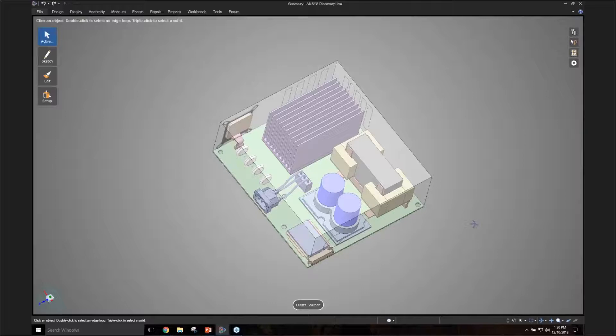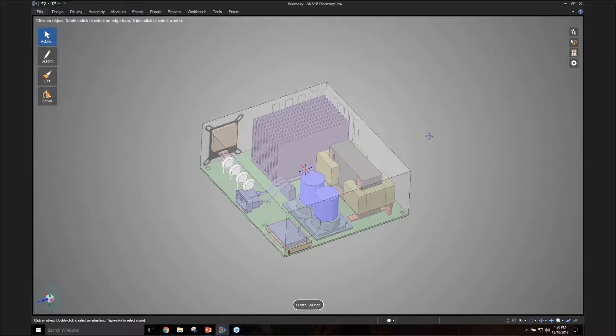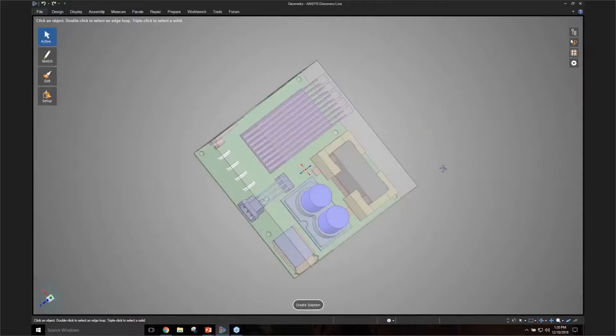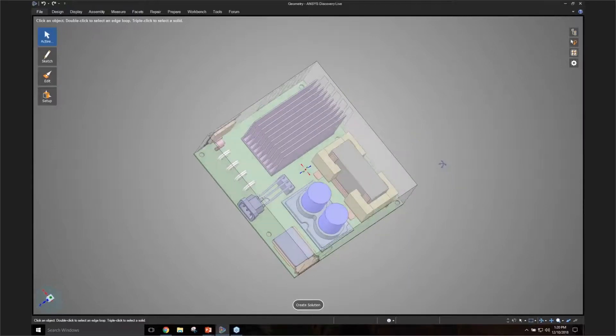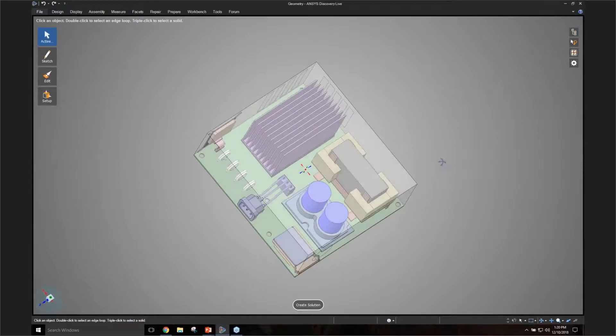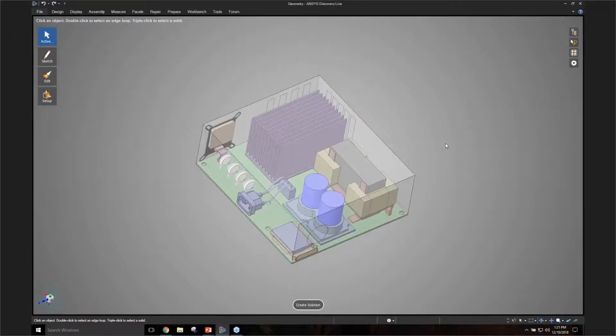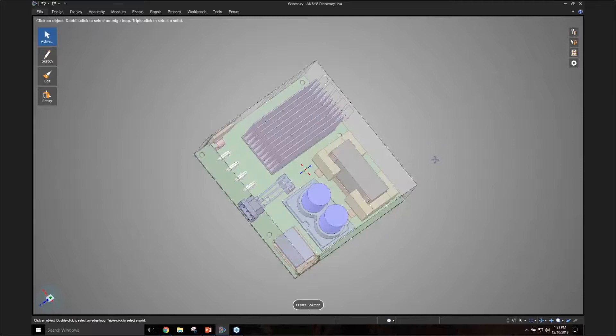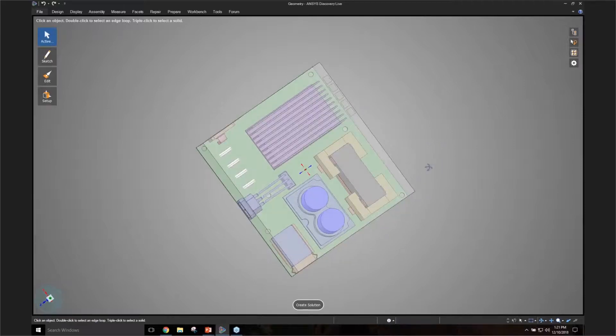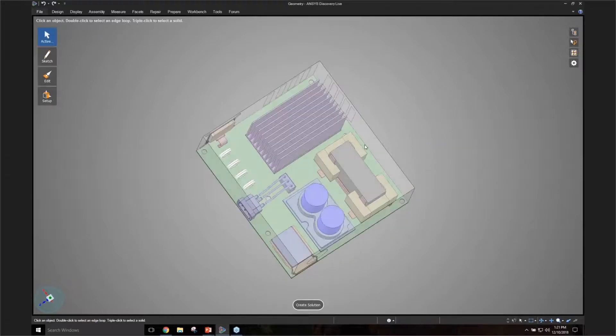When you're doing an electronics enclosure, the goal of the simulation might be to understand how to make the best use of the flow going through the enclosure. You want to make sure that most of the flow goes through the fins of this heat sink, which you see right over here.